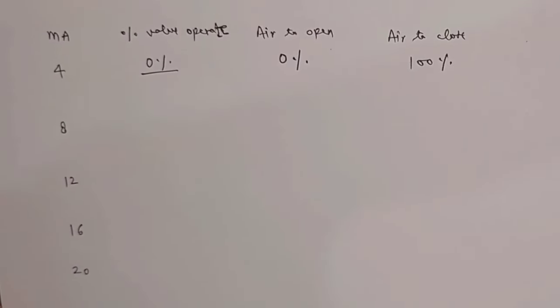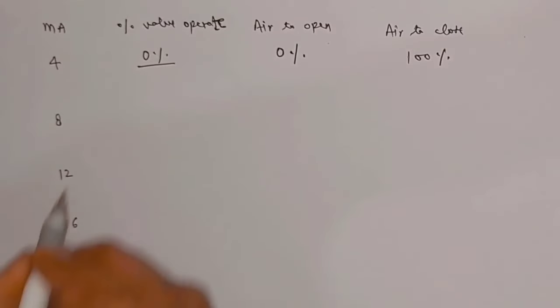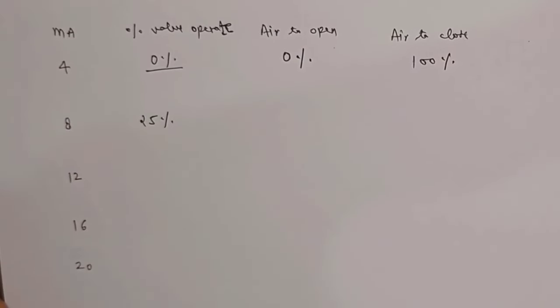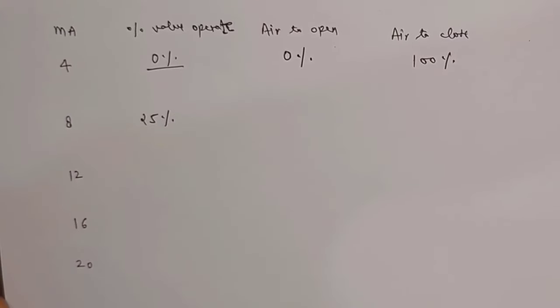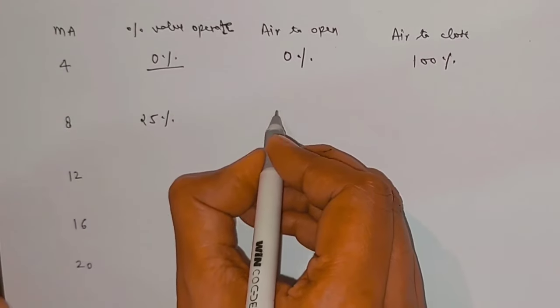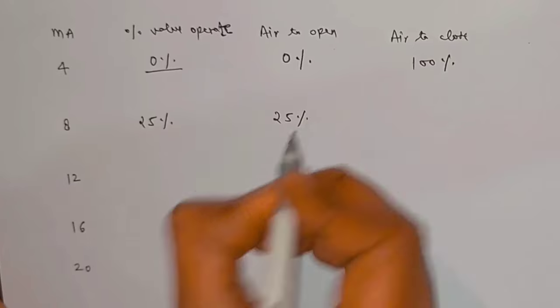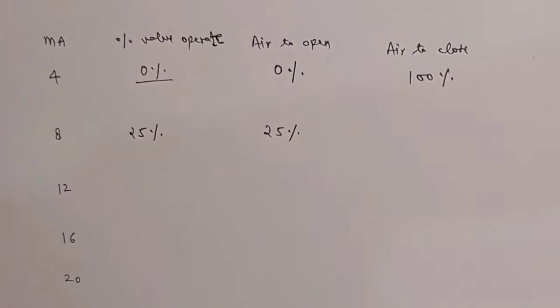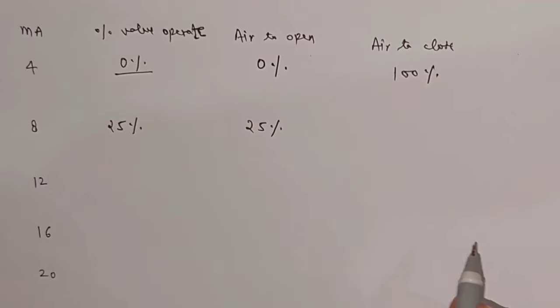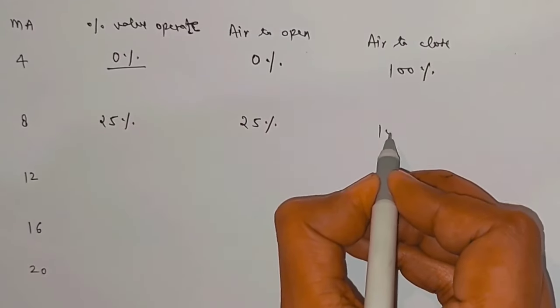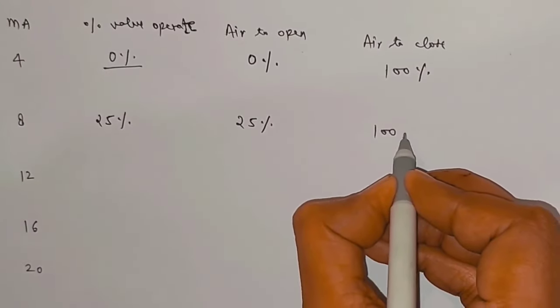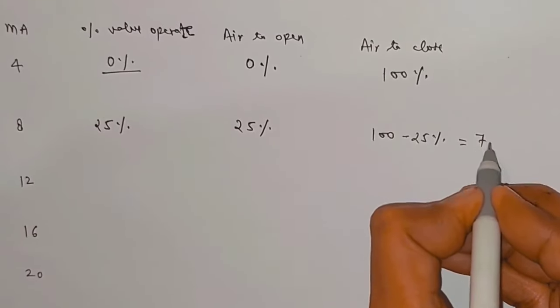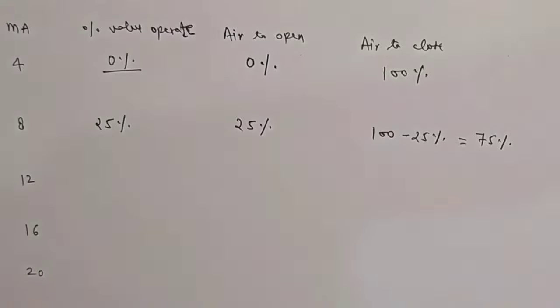Similarly, at 8 milliampere signal, the valve operates at 25%. So the opening percentage of the air-to-open control valve is 25%. Now, the air-to-close control valve will also operate 25%, so we subtract 25 from 100 — it will become 75%.